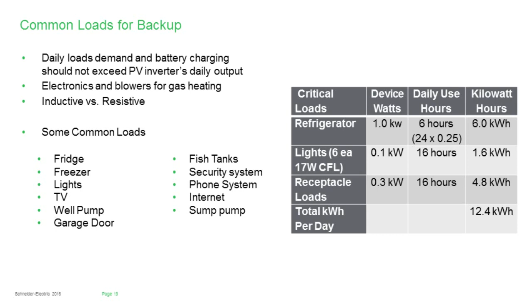Make sure people understand that whatever they plug in is going to consume that power. Just because it didn't get sized in as a receptacle load doesn't mean it won't draw power — receptacles accept anything. We need to make sure expectations are set that if large loads get plugged in, we'll consume power sooner and faster, meaning the battery bank may need to be larger if that's what the customer is going to do.